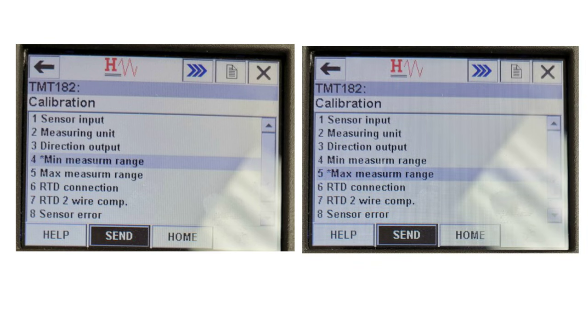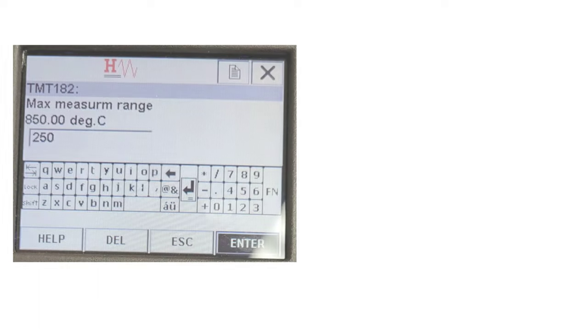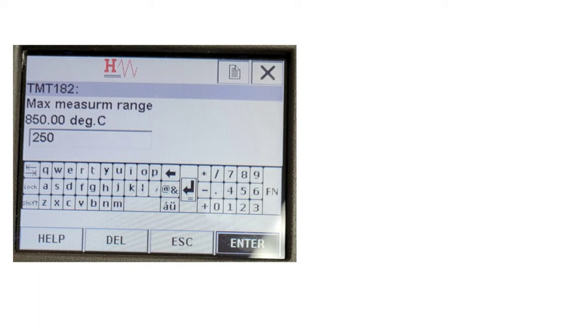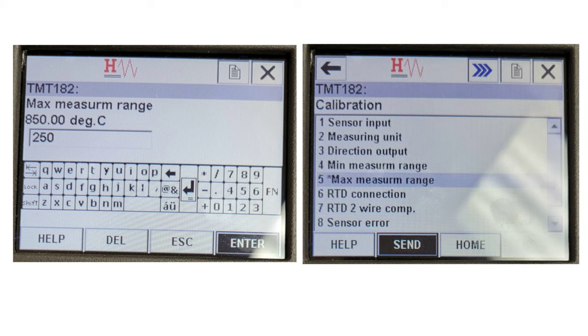Once the minimum measuring range has been sent, go to the Maximum Measuring Range option and press the ENTER button to enter that menu. In this example, the maximum measuring range is 250 degrees Celsius. Enter 250 in this field and tap Enter to confirm. Once the maximum range value has been entered, press tab twice to select Send and press Enter to send this value to the transmitter.